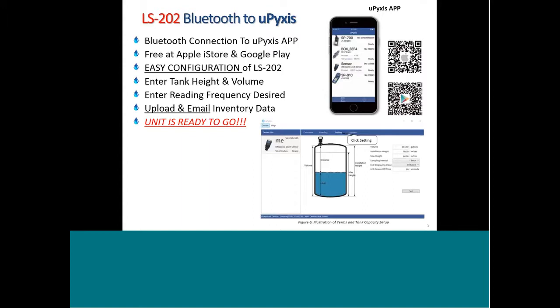It's very, very simple to configure. Once you open the app, you go to the settings function, and that'll allow you to enter some key indicators that are required in order to configure the device, including the volume of the tank that you're measuring, the installation height, which is actually the height that the meter is installed at, as well as the maximum liquid level height of the tank. And you also have the ability to adjust your sampling interval.